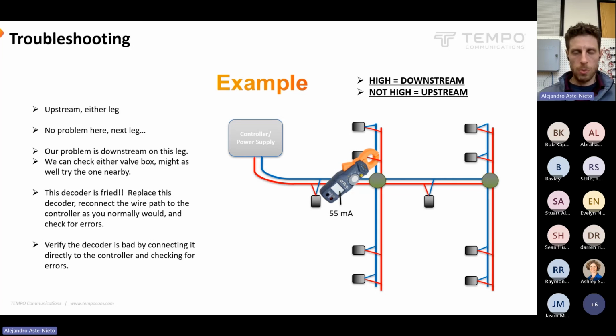And then just to talk a little bit about, what would we have done without a clamp meter in this situation? We would have had to, instead of go halfway and clamp around the wires, break half of the system off from the controller and see if that clears any errors on the controller there. Or we would have to take a measurement with a multimeter and see if we're getting the correct amount of voltage here, check and see if the resistance on this end is high like it should be, check if resistance over here is high. We'd have to take various other steps where we break the system in half and then break that system in half and keep breaking connections and walking back and forth from the controller and checking for errors. So obviously the clamp meter is a big time saver and a big saver of splices.